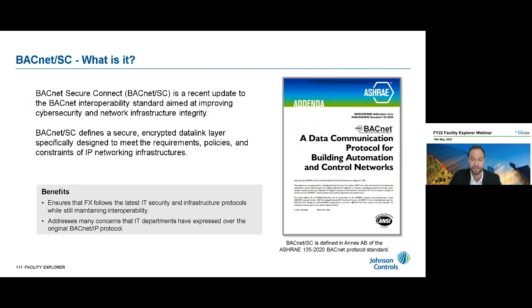Features include encrypted communication, and it's fully compatible with all existing BACnet system devices through normal BACnet routing. This alleviates IT concerns related to BMS network management. BACnet SC provides a sophisticated network security solution using standards widely accepted by the IT community. As we grow with IP networks, we see an emergence between the OT and IT worlds, and this is where BACnet SC becomes very useful.